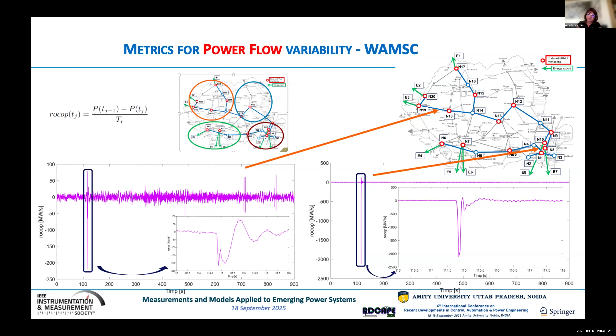We can see there are some lines that show high power flow variability in terms of coefficient of variation. This allowed us to identify, from the whole region, different subregions for the 400 kV network, where the rate of change of power, which is the variability index for each region, is different, meaning the consequences of an event might be different.